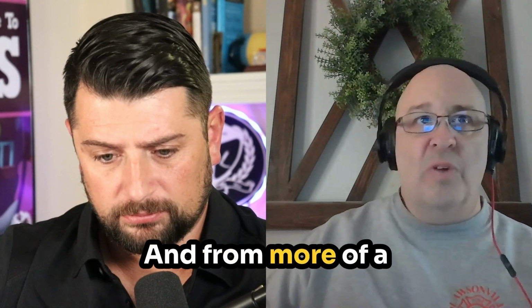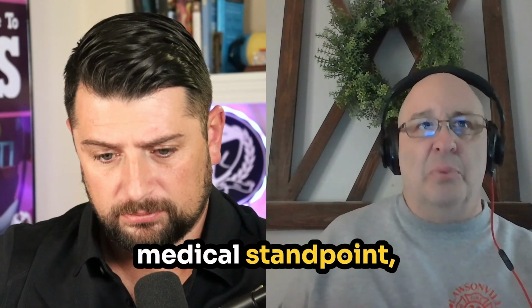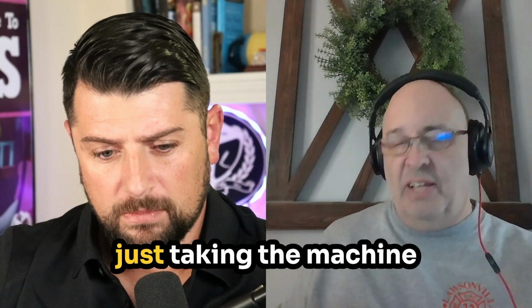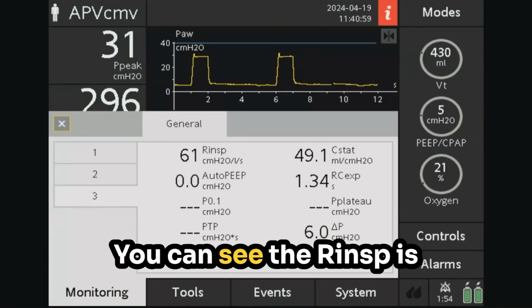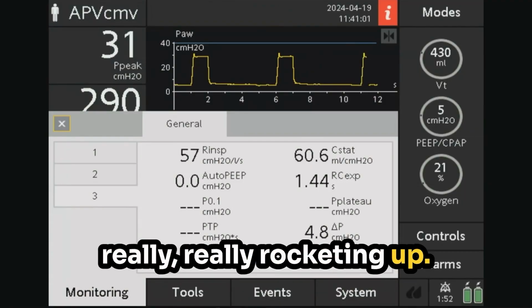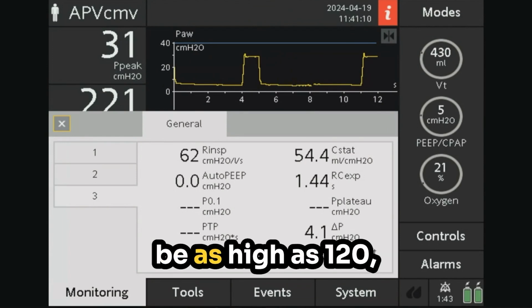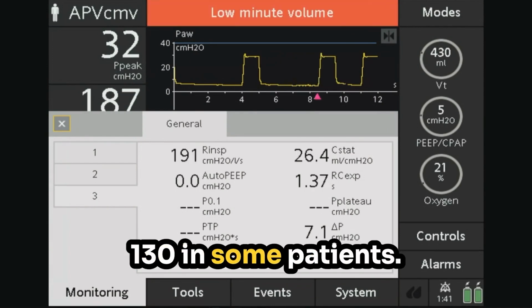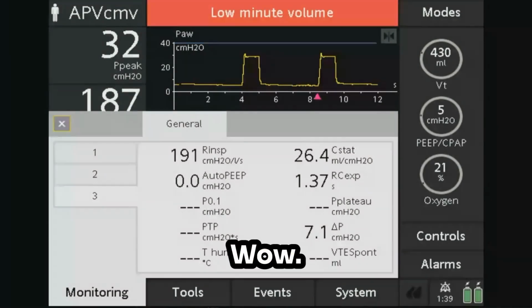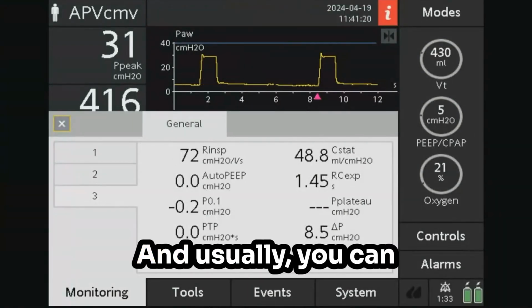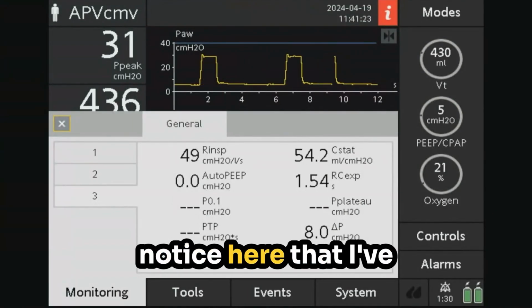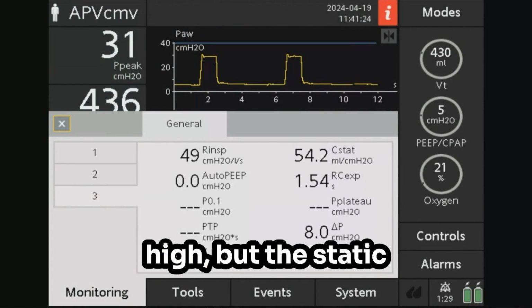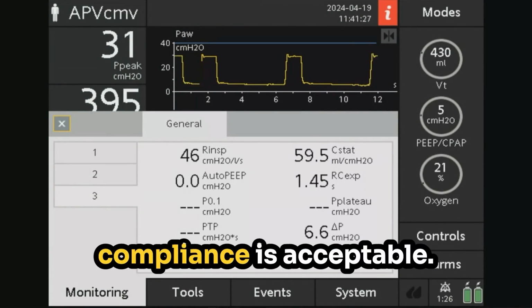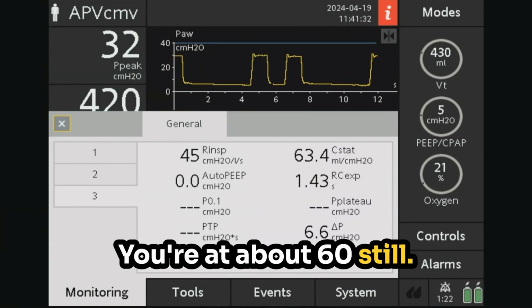And from more of a medical standpoint, I'm going to try to paint a picture for you. It's just taking the machine while they get used to it. You can see the R-insp is really, really rocketing up. I've seen that R-insp be as high as 120, 130 in some patients. Wow. That's an asthmatic. And usually you can notice here that I've got the R-insp really high, but the static compliance is acceptable. You're at about 60 still.